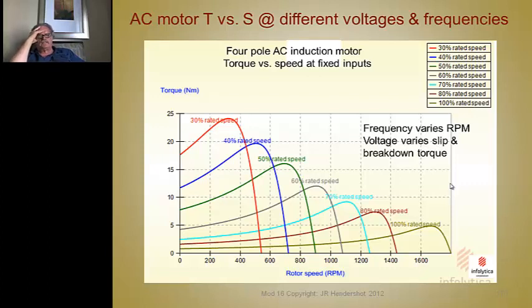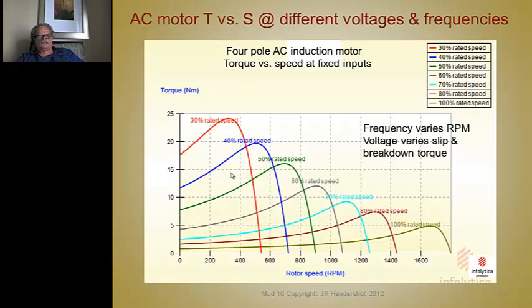So if you take that motor and use an inverter and run it at fixed voltage and frequency, and do a whole family of curves, you define an envelope of a torque speed curve of a brushless motor or a synchronous motor, which is what you want. But with constant grid voltage and frequency, you could never get the motor to perform into this envelope. So once I put an inverter on it, I can define a torque speed envelope, and that motor will run anywhere inside of this curve. Now you don't need that many curves to define that. You can do 3 or 4 curves to define that, and we're going to go over that later.